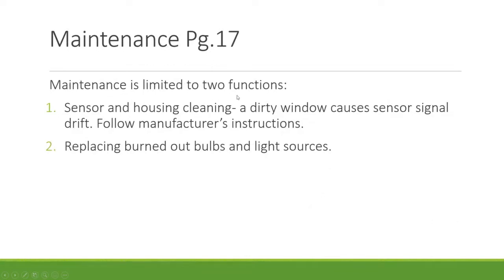Maintenance is limited to two main functions: cleaning the sensor and housing to prevent buildup that would cause sensor drift (specifically zero drift), following manufacturer instructions regarding cleaning solutions and avoiding abrasives. Some devices have automatic washers or spray jets. The other maintenance task is changing bulbs and light sources — modern electronics will notify you as the bulb ages and needs replacement.